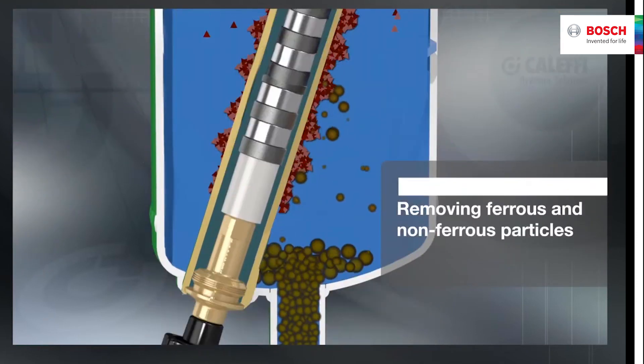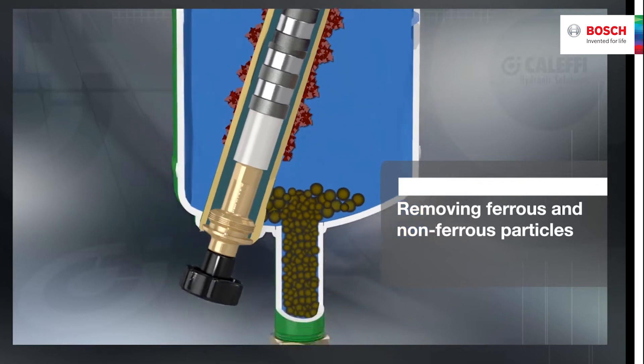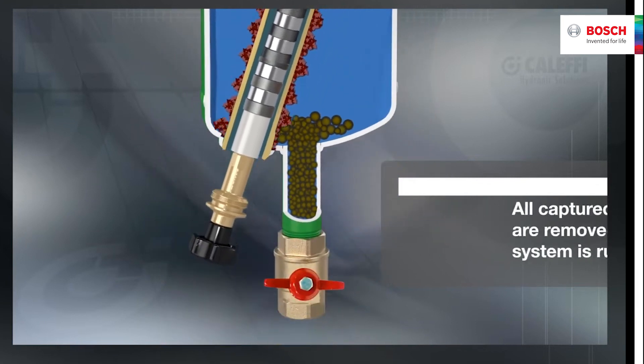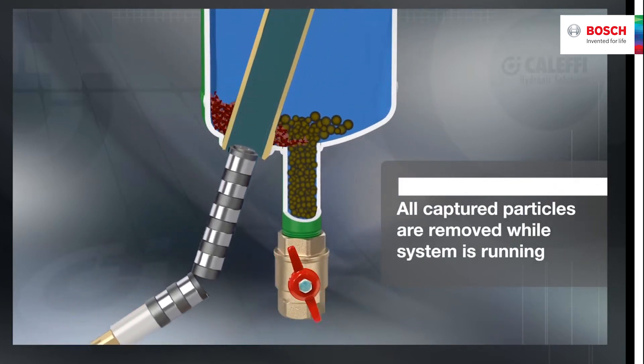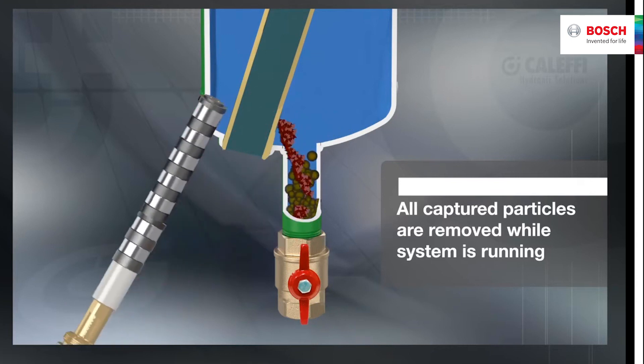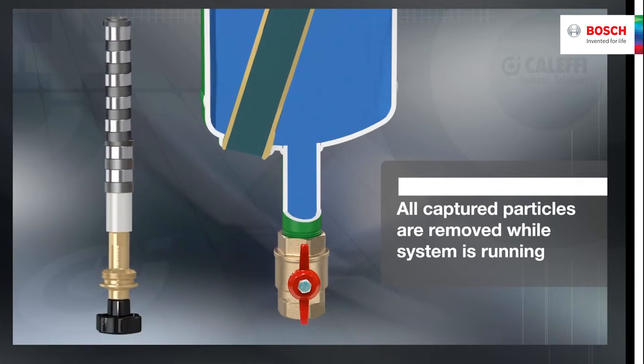Ferrous impurities including magnetite form in hydronic systems when iron or steel corrodes. Highly abrasive, these extremely fine particles are difficult to remove and can deposit onto heat exchange surfaces and accumulate in pump cavities, causing reduced efficiency and premature wear.